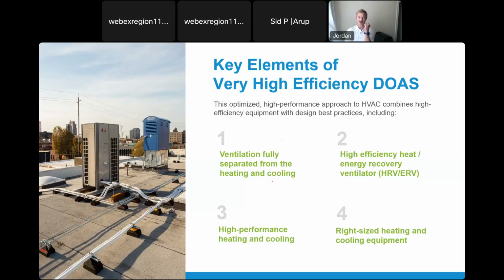Yeah, I just want to reiterate those 4 key concepts of this very high efficiency DOAS design. So again, 1, the ventilation system is fully decoupled, or fully separated, from the heating and cooling equipment. 2, a very high efficiency heat or energy recovery ventilator. 3, a high performance electric heat pump system for the primary heating and cooling system. And 4, right sizing the heating and cooling equipment to accurately account for the reduction in ventilation load that the heat recovery ventilator provides. Yeah, right sizing equipment, selecting the right tool for the job.